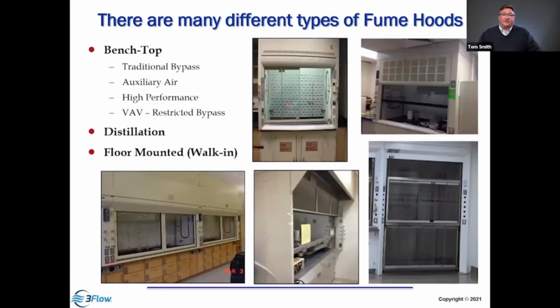As I mentioned, hoods come in all kinds of different shapes, sizes, and types. So we have benchtop hoods versus floor-mounted hoods. This happens to be a horizontal sliding sash. The panels move left to right. But we have vertical sliding sashes that go up and down. This is an auxiliary air hood. It brings air in from outside and distributes it down the face. And then over here we have a benchtop hood, but it's got dual vertical sashes, so both sashes can open independently. So we need to know the difference in these types of hoods and their design conditions so that we can properly test and evaluate the hood.